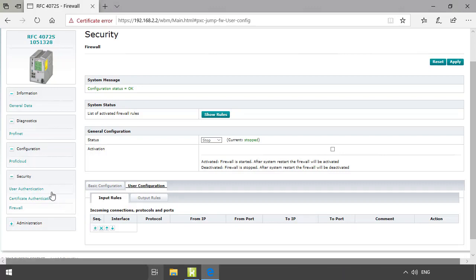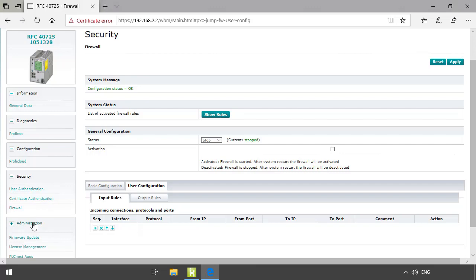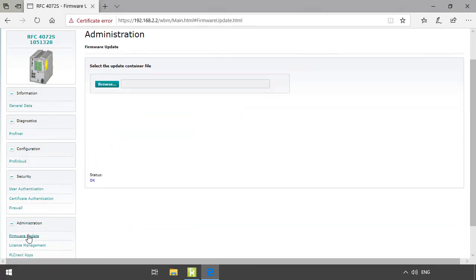Following the security area is the administration area, also divided into three different sections. The first one is firmware update. In the firmware update section you can update the firmware of the controller. You first download the desired firmware file on the Phoenix Contact website, then upload it by selecting the file and following the instructions of the installation wizard.